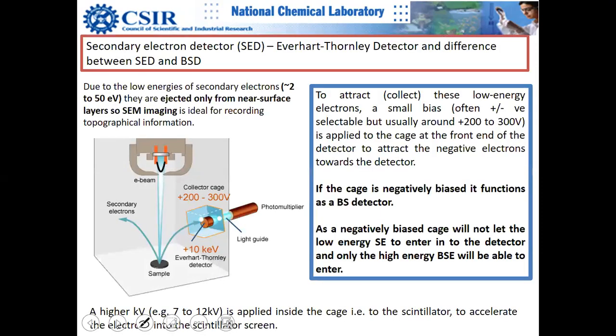Detectors are becoming much more advanced. Earlier there was only the Everhart-Thornley detector type. The collector cage has positive voltage so that outgoing secondary electrons can be drawn toward it. This is the standard detector, but it has a serious problem.